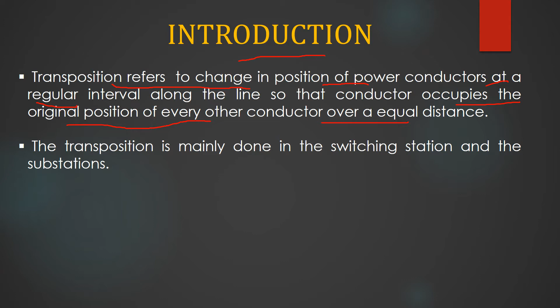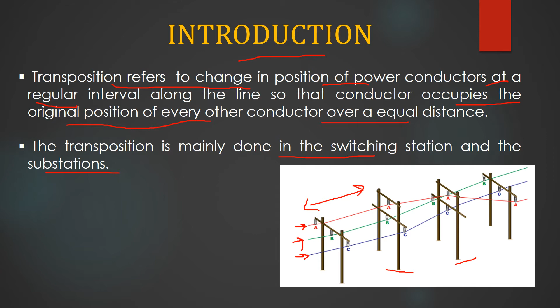The picture here depicts how the transposition is done. As you can see, the A conductor is occupying the position of every other conductor at the utility poles or the transmission towers. Similarly, conductor B and conductor C are also being transposed so that they can occupy the position of every other conductor, and you can see that the transposition is being done over an equal distance between the two utility poles or two transmission towers.